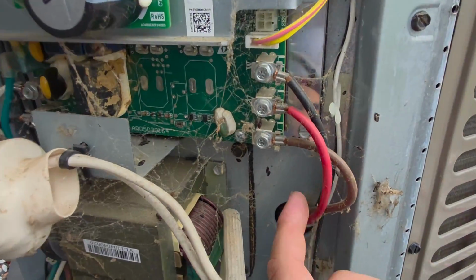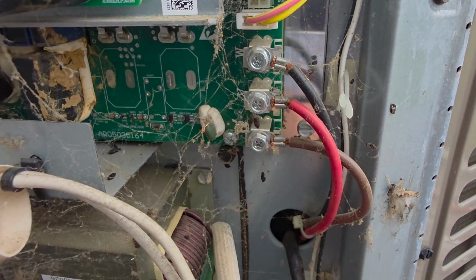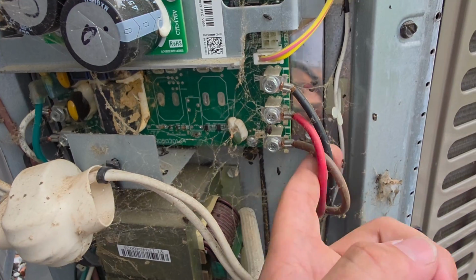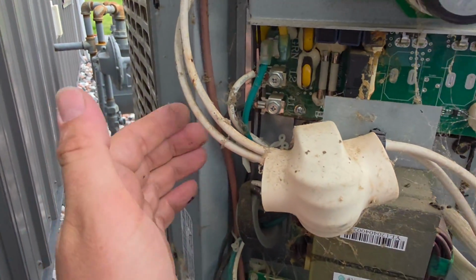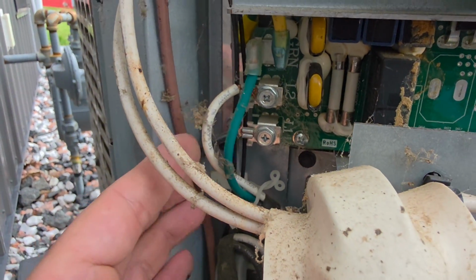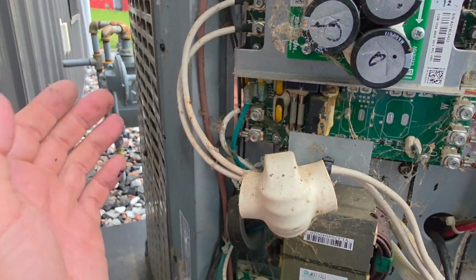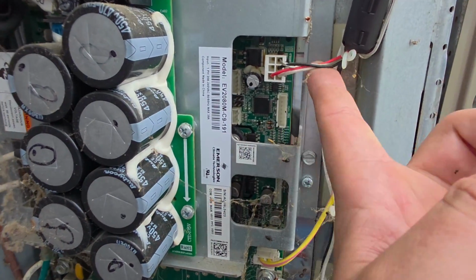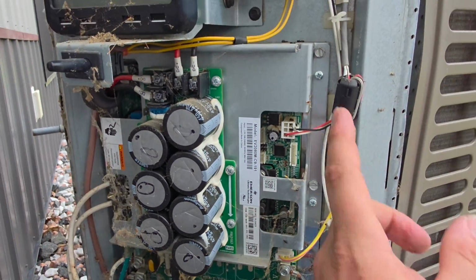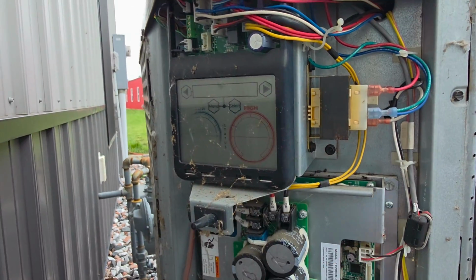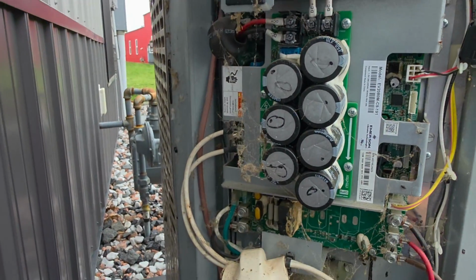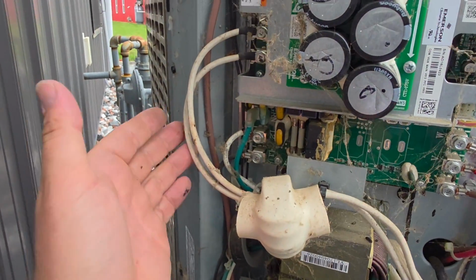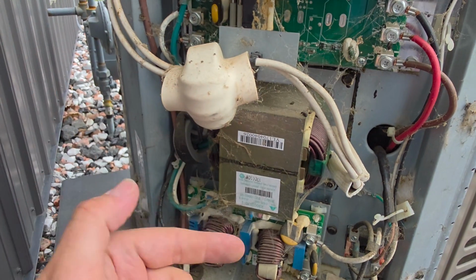We take these wires off, U, V, and W, which drive the compressor. Then we have our line voltage wires, L1 and L2, a 230 volt power supply. This plug is RS485, for communication with the master communication board. We only have a few wires, plus these that go to our reactor.